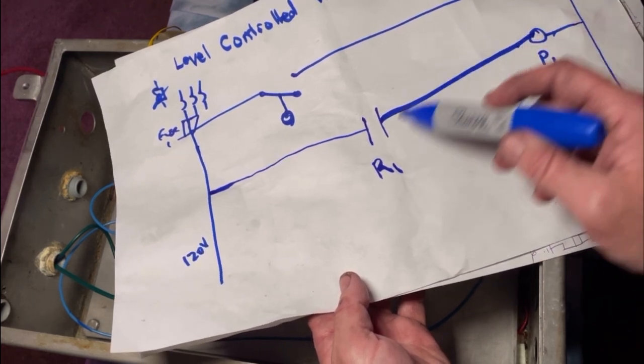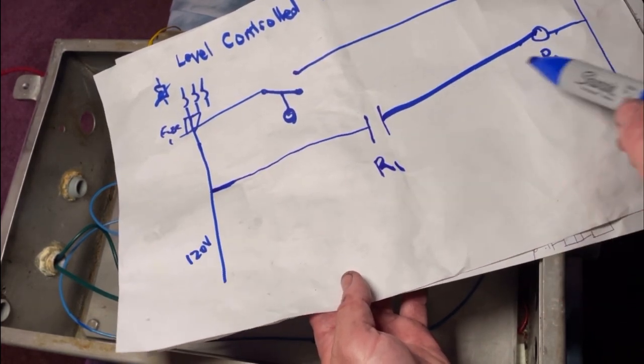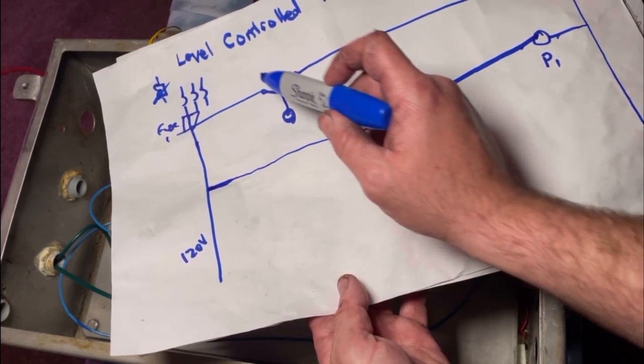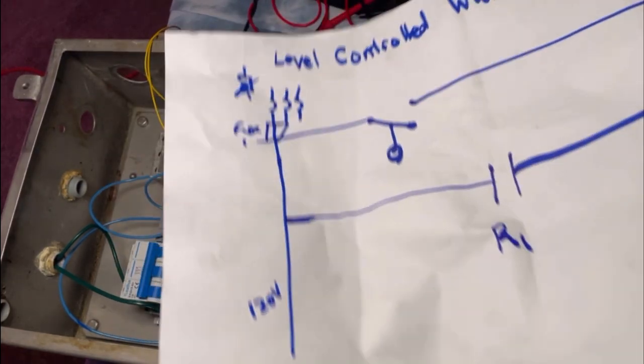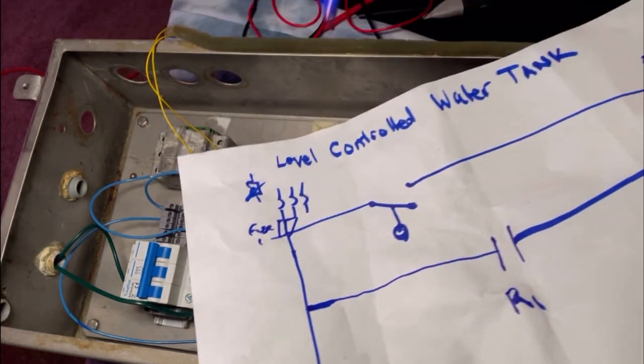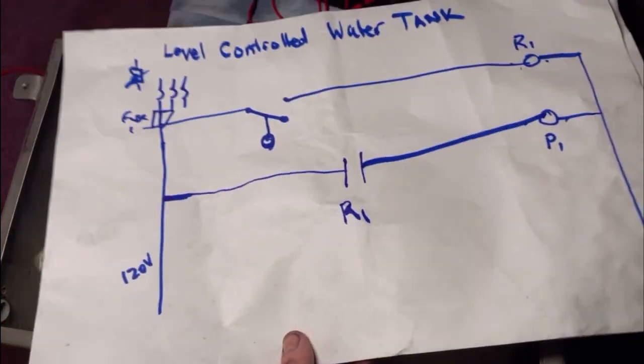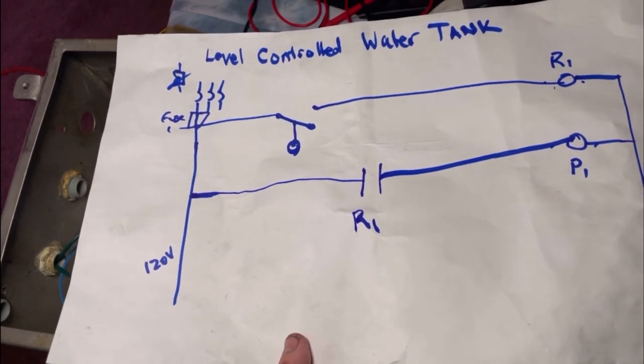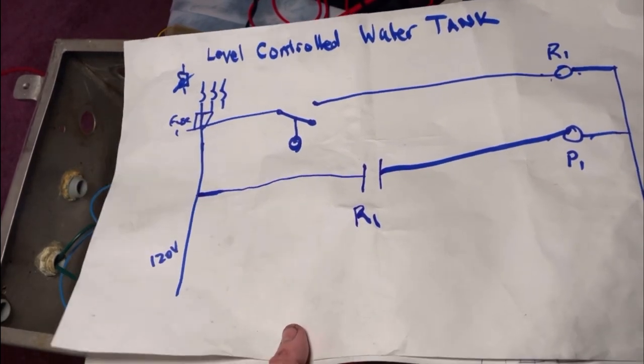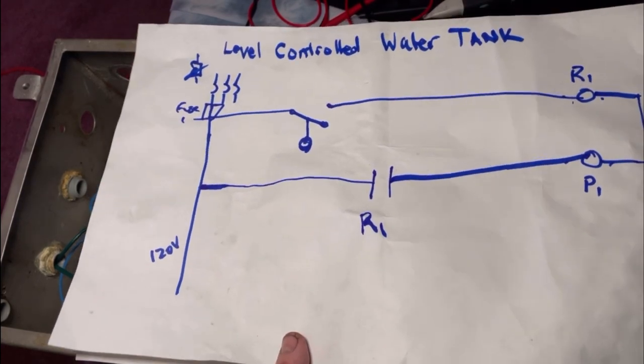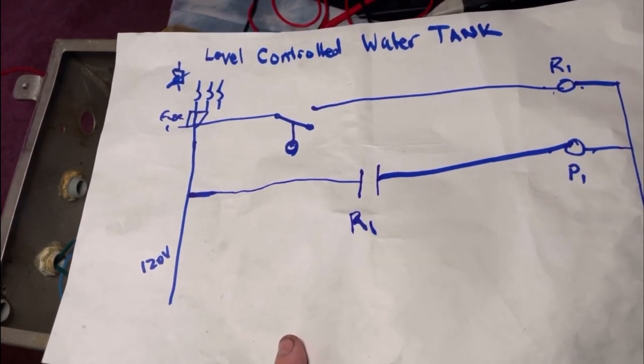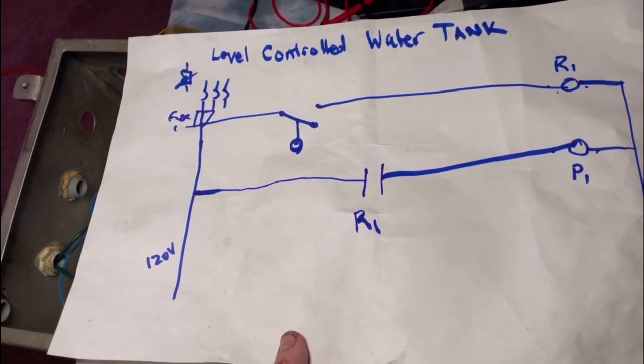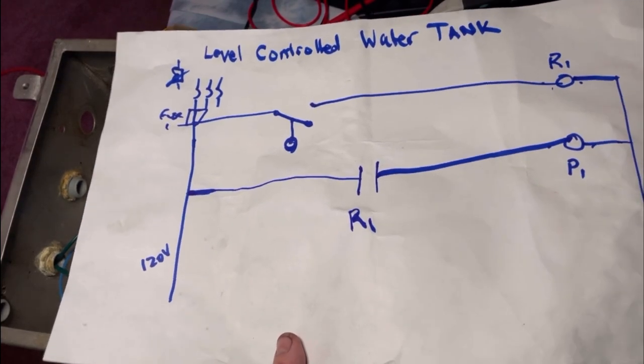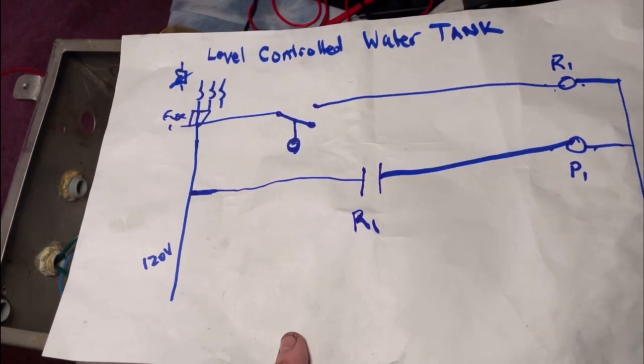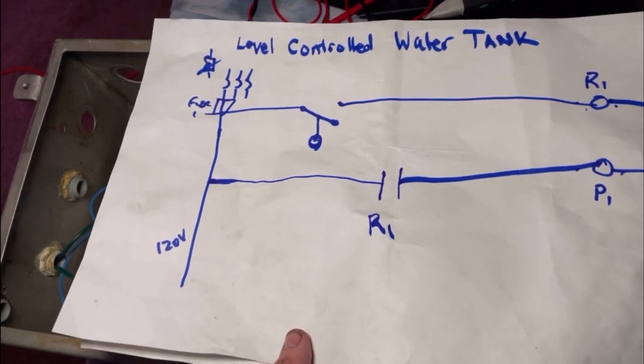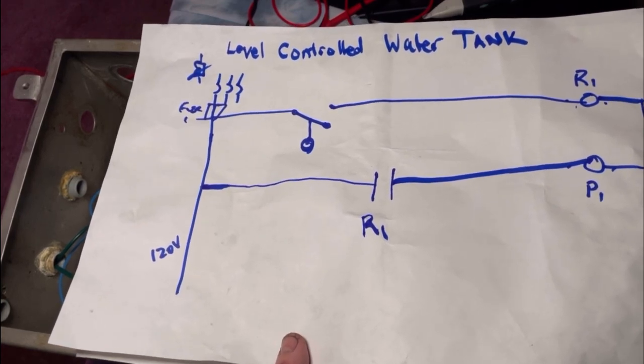Again, I'm doing it through the relay contacts because I don't want to run all the power that I'm consuming in the pump through these float switches. I could just go float switch right to pump 1, but I mean, that's really thin wire. Realistically, it would probably work, but I'm showing you guys what they do in the industry. You run power, like motors and pumps. You either run them through relays if they're really small motors, but usually what you do is you run it through a contactor or a starter. But on this one, we're just going to run it through a relay. A lot of stuff gets, smaller loads get run through relays generally. So let's wire that up real quick and then I'll show you the lift station. There's more things that can be improved and we'll go through them after that.